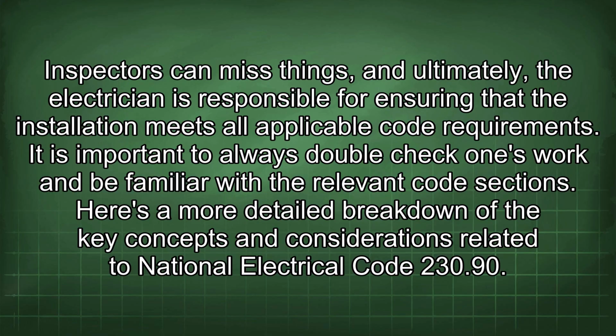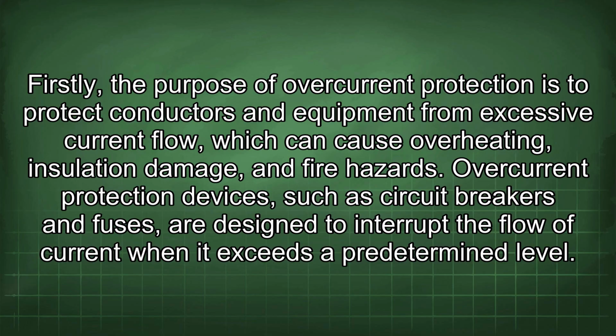Here's a more detailed breakdown of the key concepts and considerations related to National Electrical Code 230.90. Firstly, the purpose of overcurrent protection is to protect conductors and equipment from excessive current flow, which can cause overheating, insulation damage, and fire hazards. Overcurrent protection devices, such as circuit breakers and fuses, are designed to interrupt the flow of current when it exceeds a predetermined level.